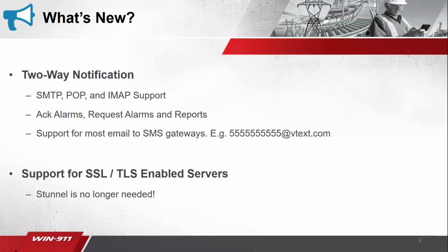What's new with the email notifier? The main thing would be two-way notification. You can send mail out to alert your operators, but you can also reply to those messages to ACK alarms or request alarms or request reports. We support SMTP servers to send mail out and POP and IMAP servers to receive mail.